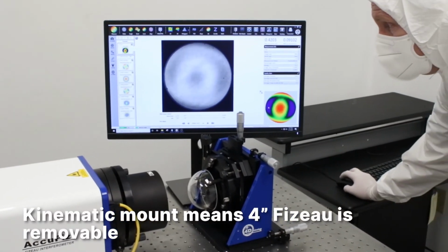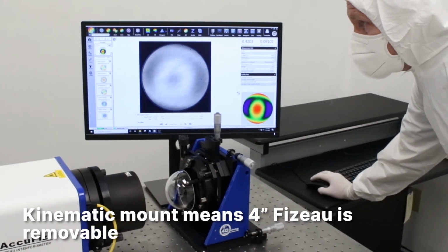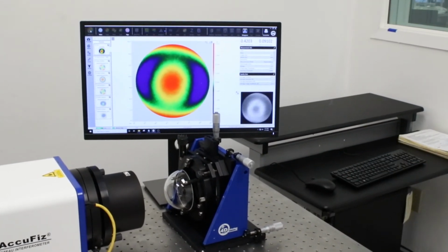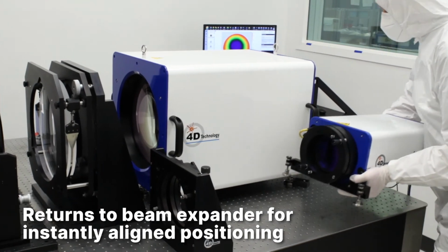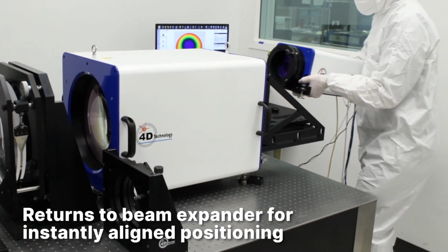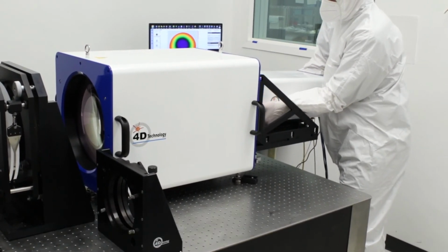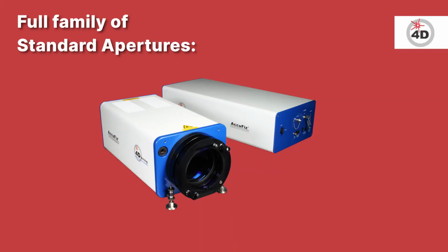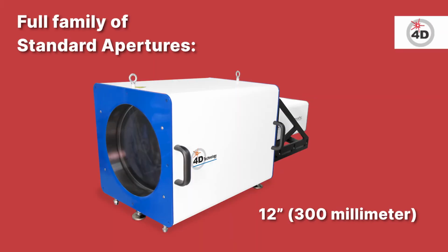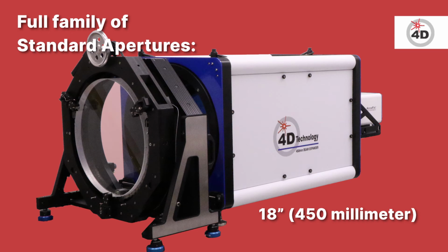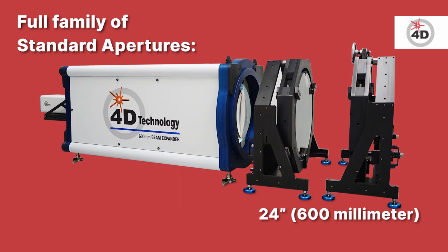The on-axis beam expander's kinematic mount means you can use the interferometer mainframe as a standalone device, then remount it back into perfectly aligned position. The AccuFiz D can be ordered with any of the standard apertures: 4-inch, 12-inch, 18-inch, or 24-inch.